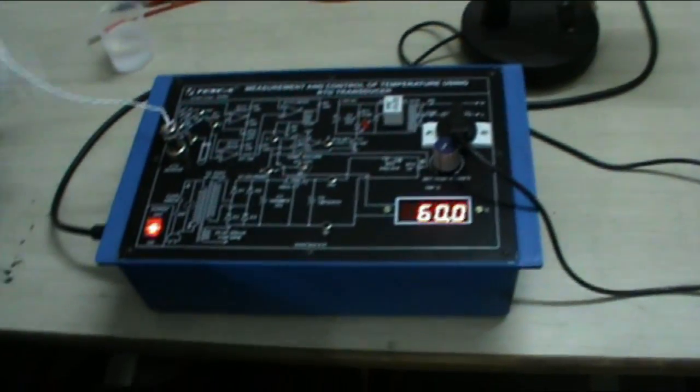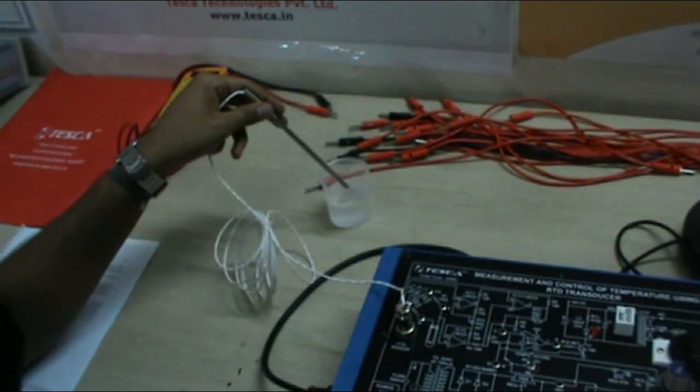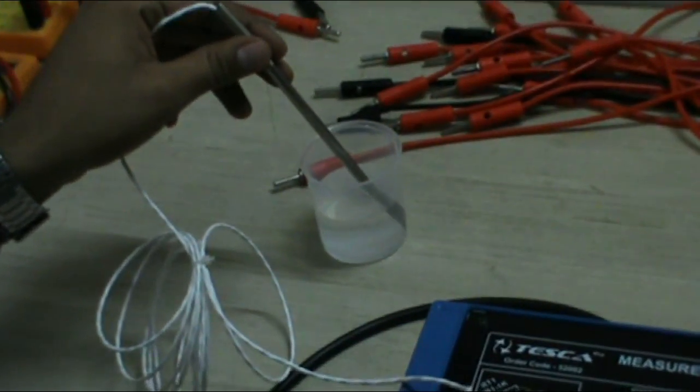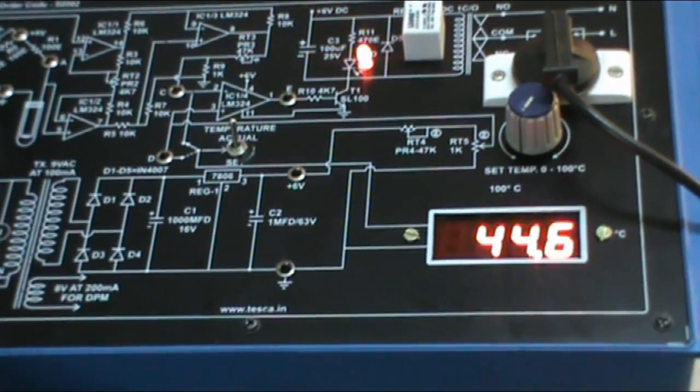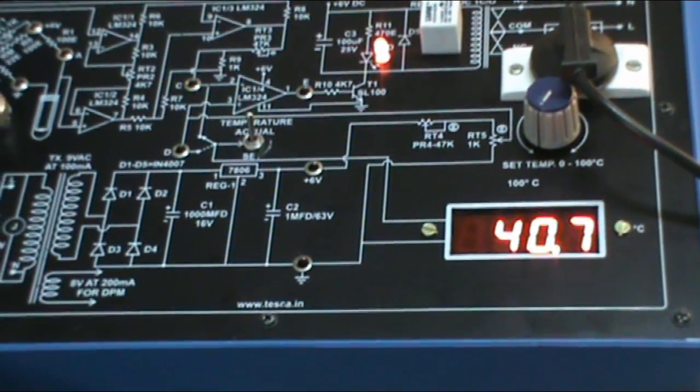As you can see, as it crosses the 55 degrees, the lamp is off. Now when we cool down this RTD sensor with the water, you can see the temperature will come down, and as it comes below 55 degrees, the lamp will glow again.